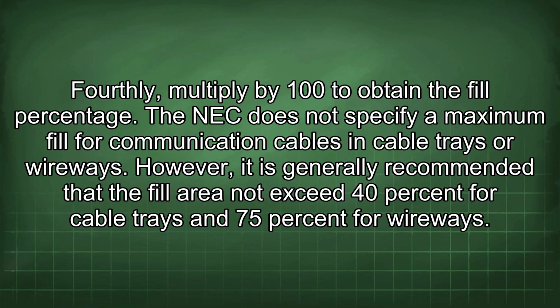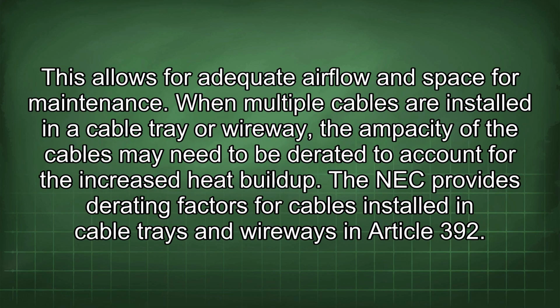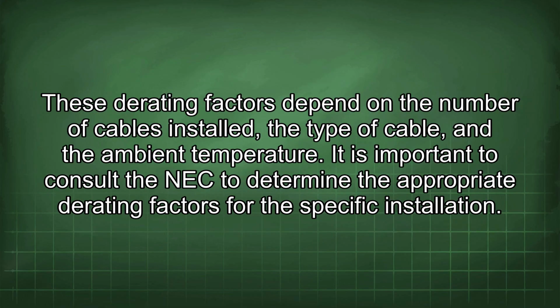The NEC does not specify a maximum fill for communication cables and cable trays or wireways. However, it is generally recommended that the fill area not exceed 40% for cable trays and 75% for wireways. This allows for adequate airflow and space for maintenance. When multiple cables are installed in a cable tray or wireway, the ampacity of the cables may need to be derated to account for the increased heat buildup. The NEC provides derating factors for cables installed in cable trays and wireways in Article 392. These derating factors depend on the number of cables installed, the type of cable, and the ambient temperature. It is important to consult the NEC to determine the appropriate derating factors for the specific installation.